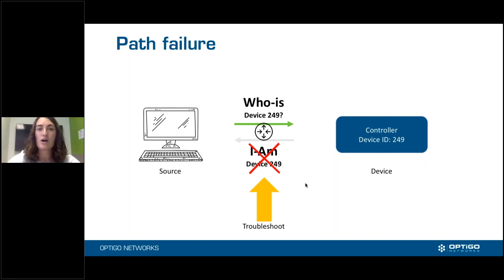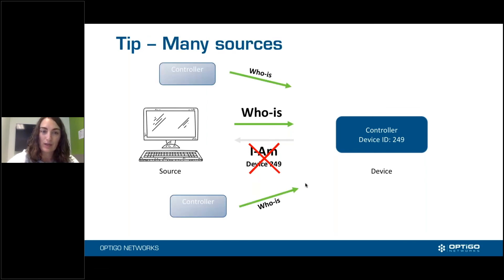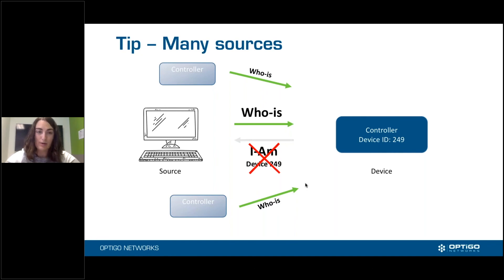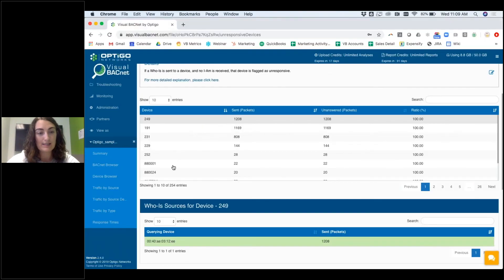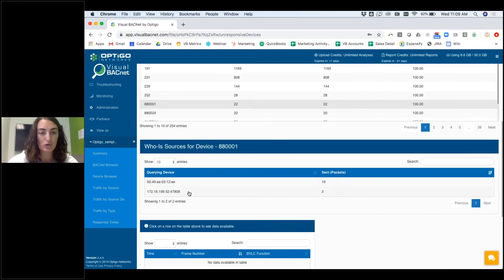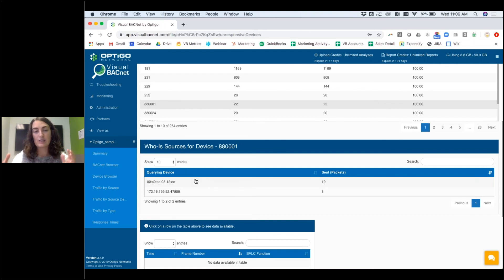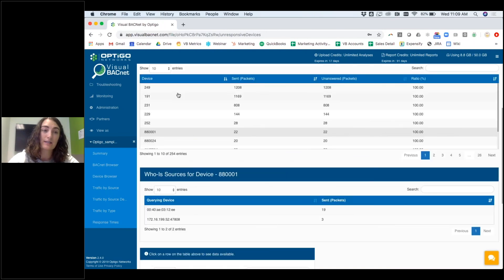This routing scenario is by far the most uncommon. Often it's a source device looking for something erroneously, or a destination device is offline. One last tip: if you have no device list and no idea whether a device should be on the network, look at how many source devices are querying it. If you go into Visual BACnet and see eight different devices sending Who-Is to a single destination, it's quite likely that all those devices are programmed to look for it — meaning the configuration is correct and the destination device has failed.